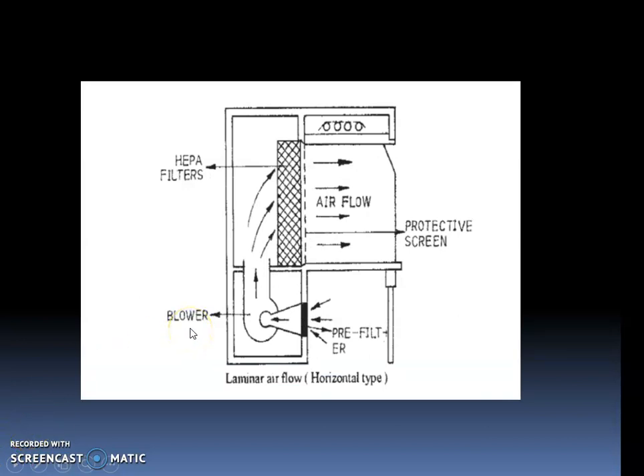Then HEPA filters. They ensure the laminar airflow and remove particles as small as 0.3 micrometer with 99.97% efficiency. HEPA stands for High Efficiency Particulate Air. This is a laminar airflow bench, meaning a horizontal laminar airflow bench. It has a blower and a pre-filter from where the air is filtered. From the blower it is blown to the HEPA filters, and the HEPA filter will filter that air, which will move to the cabinet or protective screen, and this air will be the aseptic air. Under this aseptic air, we are supposed to seal and fill our containers with the sterile formulation.